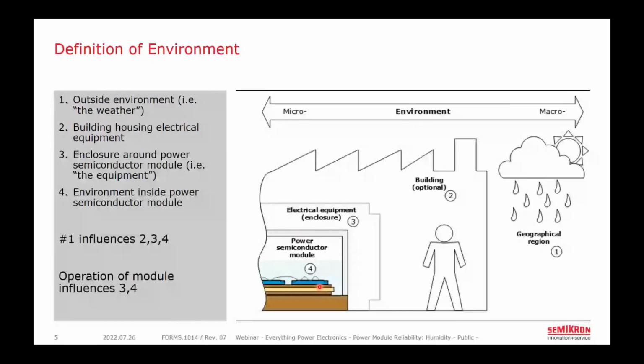The effect of this outside environment is usually dominant. So it's expected that if you're in a tropical region where there's a passing thunderstorm, it will yield high humidity within the electrical equipment or power module. What's less apparent is how the electrical operation of the power semiconductor module influences the environment immediately around it. As we will discuss, the heating and cooling of this power semiconductor module can actually generate high humidity conditions immediately in the microenvironment in and around the module, even if the conditions in the building or outside seem relatively dry to a human observer.